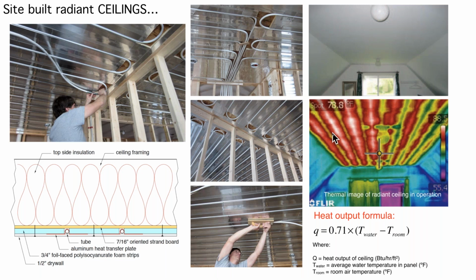Literally, that will triple the output compared to just putting the tubes up without any type of heat transfer plates involved. And then if you're looking at a system like this, and by the way, this tubing is all 8 inches on center, the output of that particular system would be this. It'd be the average water temperature in the circuit minus the room temperature times 0.71. And let's say the average water temperature was 110, the room's at 70, so we've got a 40-degree differential here. 40 times 0.7, we're getting about 28 BTUs per hour per square foot with a relatively low water temperature.